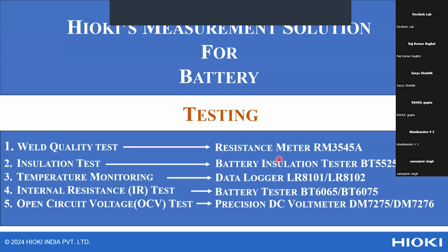Just like first one, a resistance meter for weld quality test, a battery insulation tester for the insulation test between electrode and case, a data logger for recording of voltage and temperature, and after that a battery tester for checking the IR of a battery, and a DC voltmeter for open circuit voltage testing. So I will explain all these one by one.